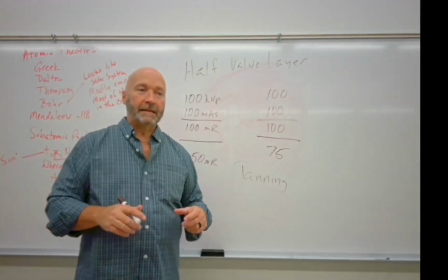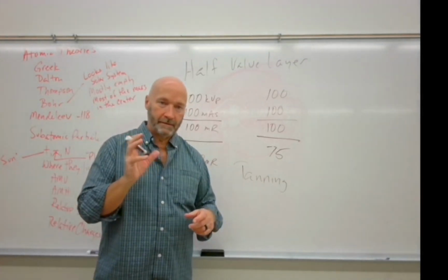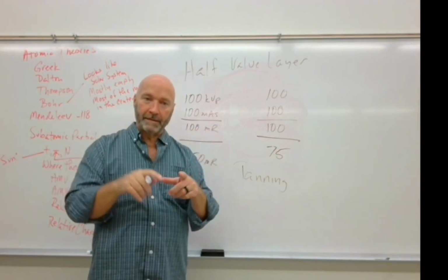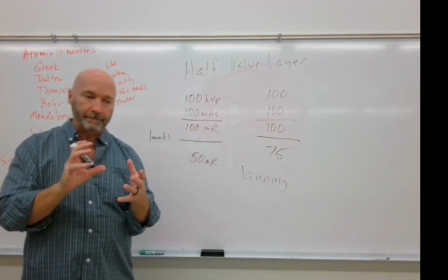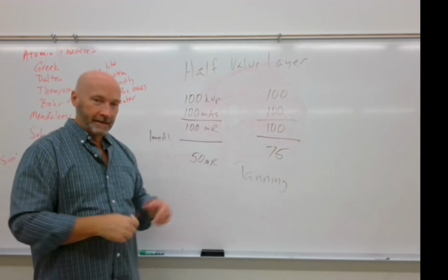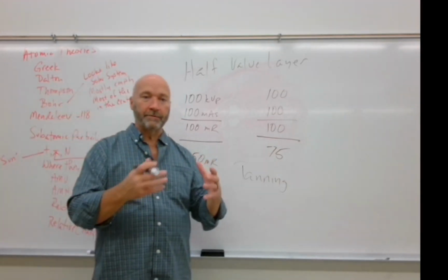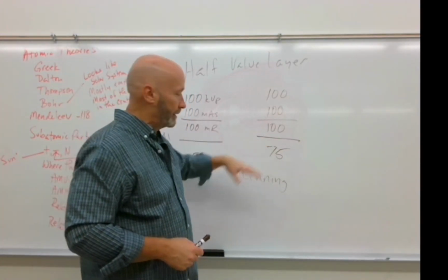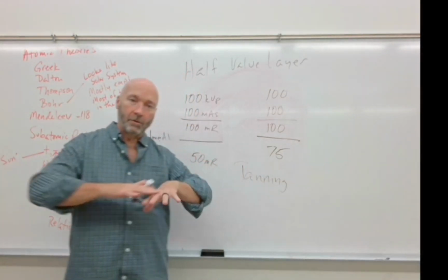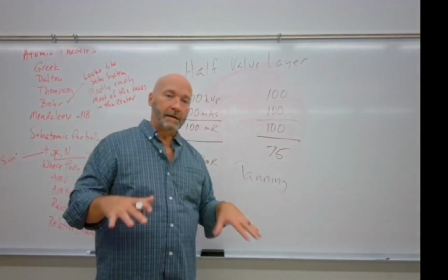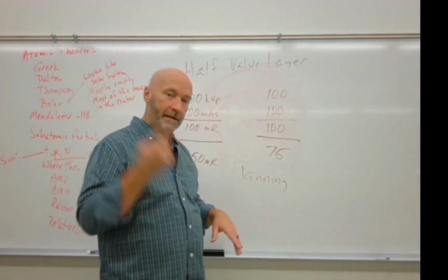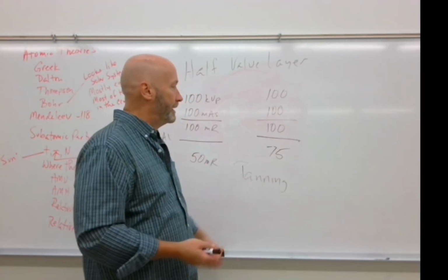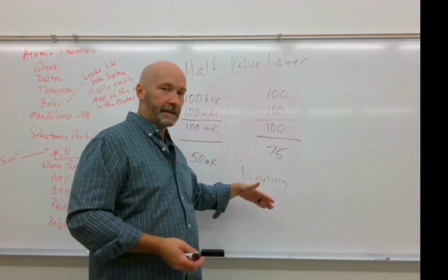Tanning is when you unscrew that incandescent light bulb and you see that blackening of the glass right before the base where the light bulb screws in. That's basically tanning. It's vaporization of the filament that coats the inside of the X-ray tube. So if this machine has been used for a couple of years, some of that filament is going to coat the inside of the X-ray tube with tungsten, and that's going to increase the filtering ability of that X-ray tube, and it's going to reduce the intensity.